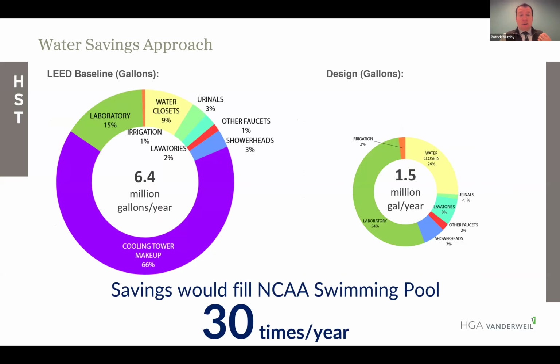In total, the effect was that baseline used about 6.5 million gallons per year. The proposed design reduced that to 1.5 million gallons a year. And that's enough water to fill Lehigh's swimming pool for their swim team 30 times a year. So pretty dramatic savings. And the two main strategies that we used were eliminating the cooling tower and recycling or reclaiming that roof rainwater and HVAC condensate to use it for some of the loads in our building.